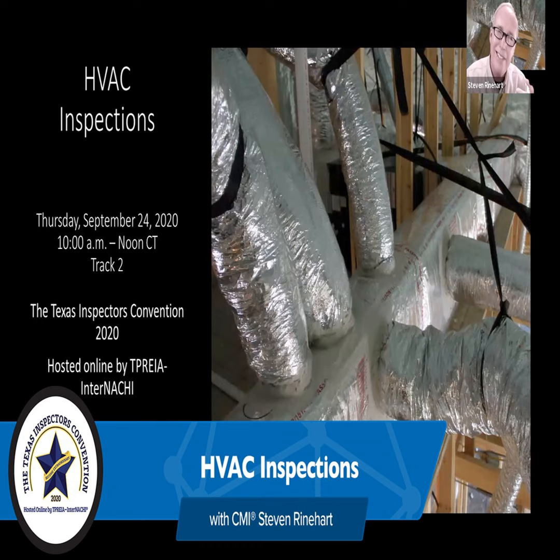And some municipalities, Colleen, I think they prohibit it because the aggregate condensation from 50,000 air conditioning units puts a lot of extra water on the sewer treatment plant that does not need treating. So they actually do not want you, especially in the commercial world, putting the condensation drain in your sewer. It just adds to the load of the treatment plant. So they looked at it that way.